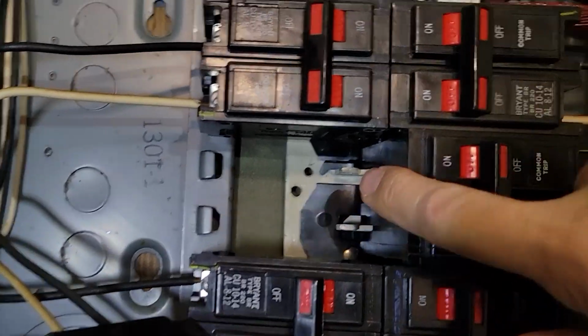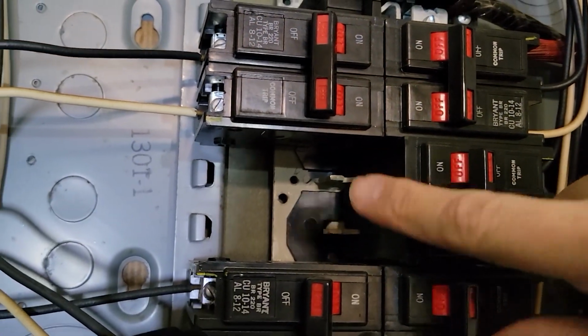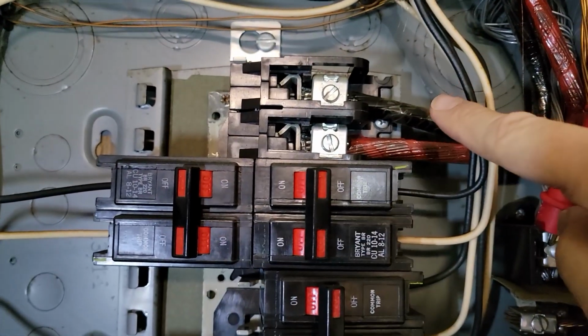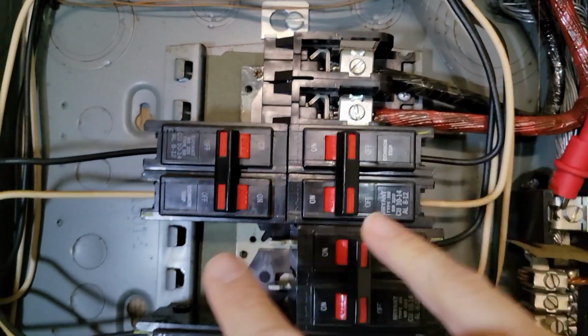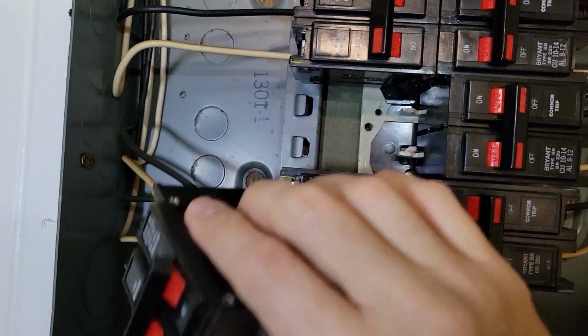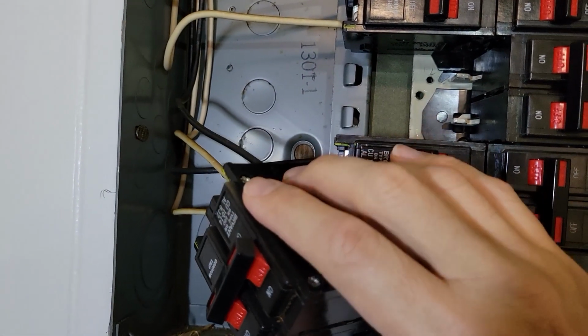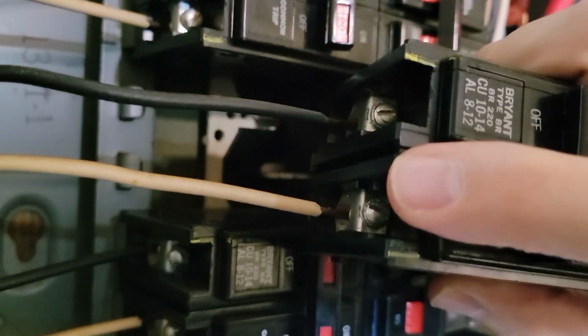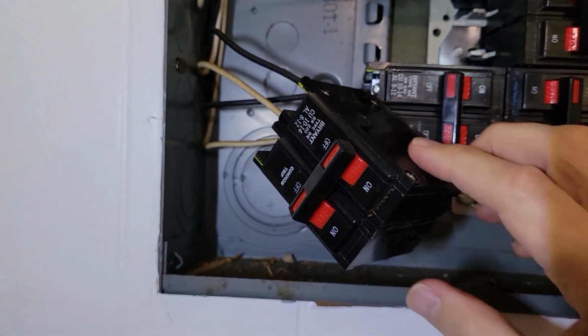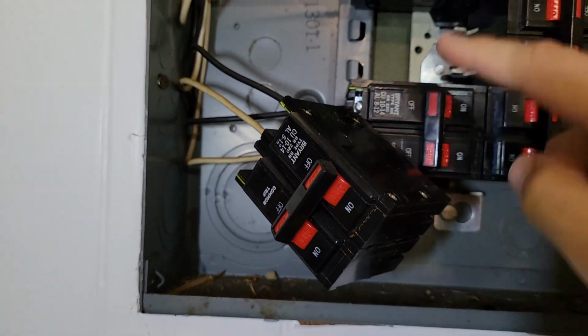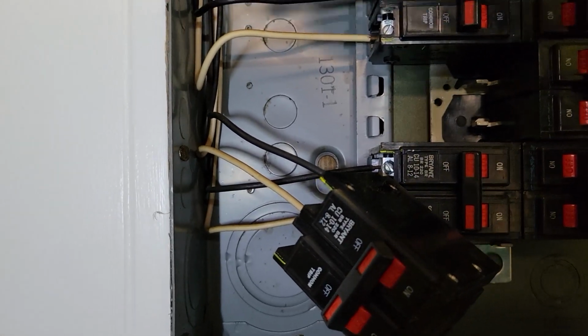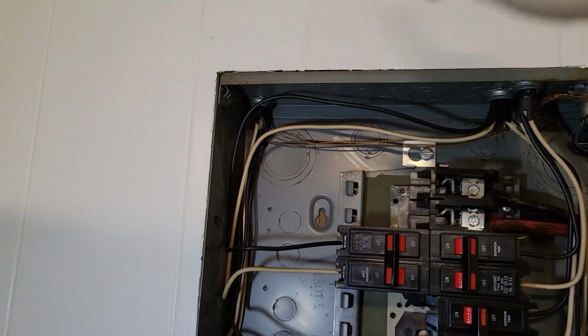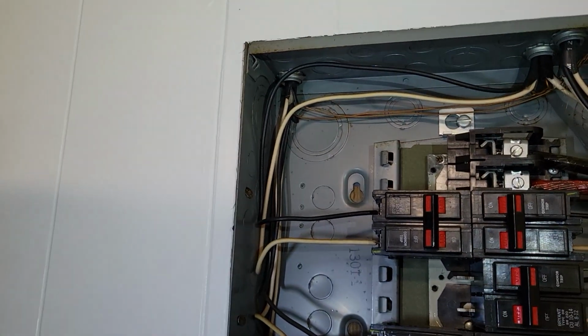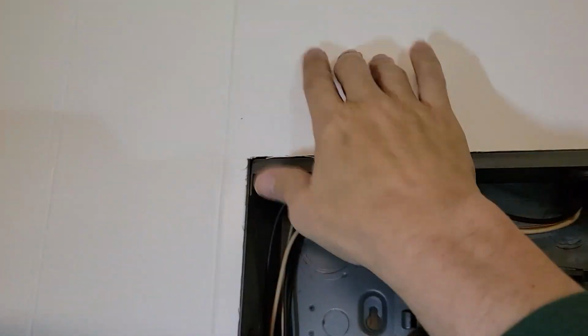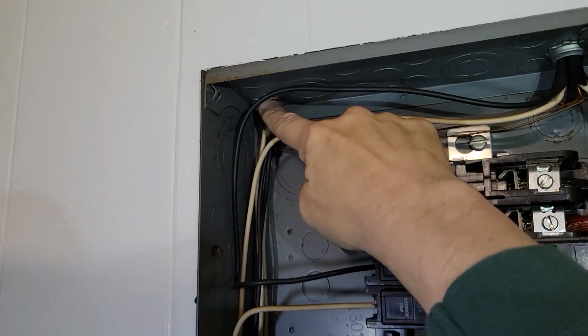There's a contact, and there's the other contact from each side of the bus, because that's 120, 120. Because they're being shared on one circuit breaker, that's how you get 240. So what I'll do is, there are screws right there. I will remove those screws, and then I will put in my 50 amp circuit breaker here, and then I will run my line up. Usually you run the line in, but in our situation, I'm not going to tear this out to do that. So I will break that connector loose.